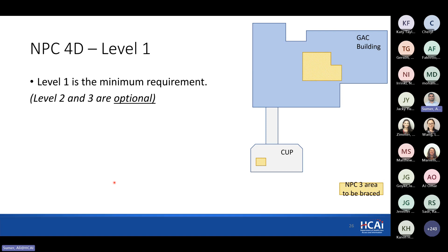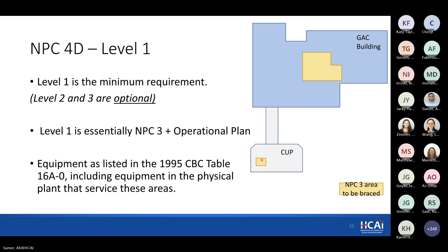Level 1, again, as I showed on different graphics, is the minimum requirement. Level 2 and 3 are optional. And again, the critical care area bracing at your building and the source is required on NPC 3. Level 2 is basically, first you need to be compliant with level 1 items, plus the utilities from the critical care area to the source need to be braced. So the bracing is not just within your building in question, it goes all the way to the source. If it goes to another building, you just follow it all the way through to that building.